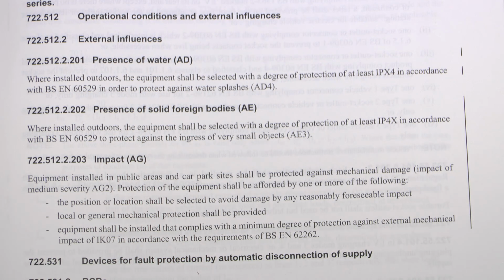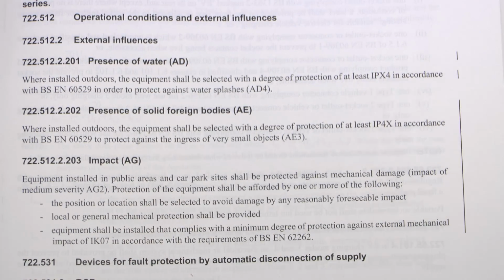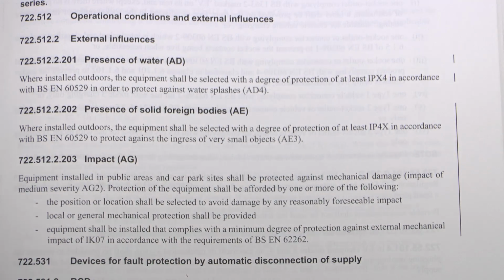And some options here: position or locate to avoid damage by any reasonably foreseeable impact, local or general mechanical protection to be provided, and equipment to be installed that complies with a minimum degree of protection against external mechanical impact of IK7, and again in accordance with the standard here. So quite a lot of extra stuff there. Bearing in mind this stuff is going to be installed outside in terms of charging equipment, there's going to be vehicles moving close and around it, so again, pretty sensible to have these things in there. And this here, which is the part on RCDs, is 722.531.2.101.